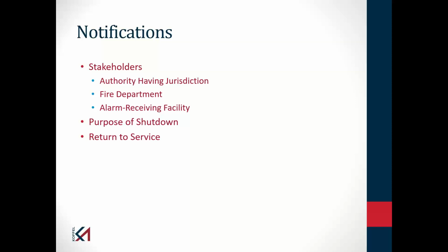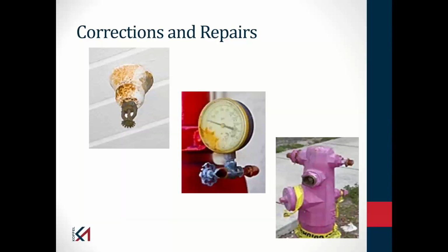Many insurance carriers require you to put a tag on the system, an impairment tag, telling me when it was impaired and when it was put back in service. When it's put back in service, the impairment tag should be removed, and you should do a valve test, which is typically a main drain test or some drain test, to verify that the valve is now back in the open position. But these notifications generally are the responsibility of the owner. The owner is responsible for corrections and repairs.